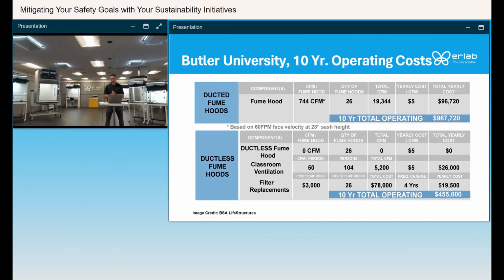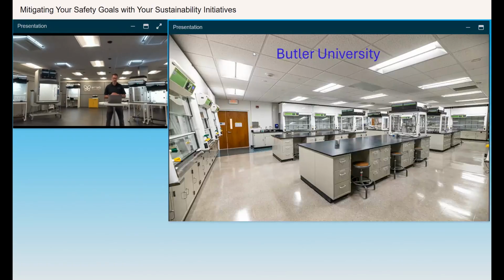Versus running 26 ducted fume hoods, they had a constant volume system, so they were all going to be at 744 CFM the whole time. They were going to cost them about $96,000 a year. With the ductless fume hoods, they were changing the filters every 4 years. So even with the cost of filter changes, they saved about $500,000 over the course of the 10 years.